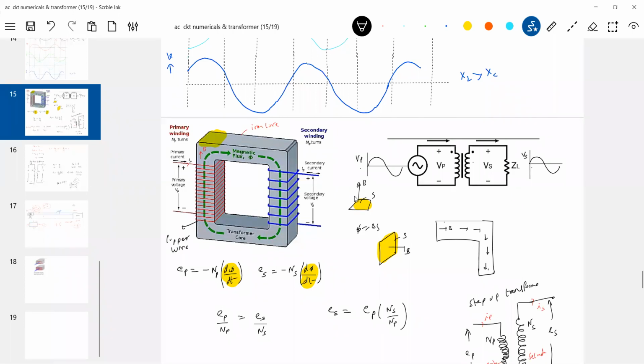And we know whenever a current flows through a metal, heat should be generated. So there'll be heat. To minimize these losses due to I square R in the windings, what shall I do? Go for R equal to rho L by A. So what sort of copper wire should I use for winding? A thicker one. If I increase the area of cross section, resistance will decrease. If resistance decreases, I square R in the winding decreases.